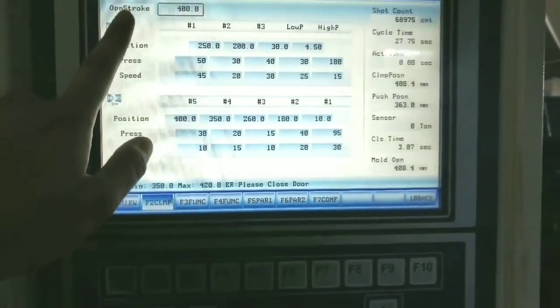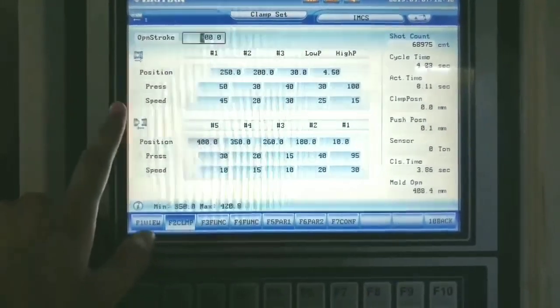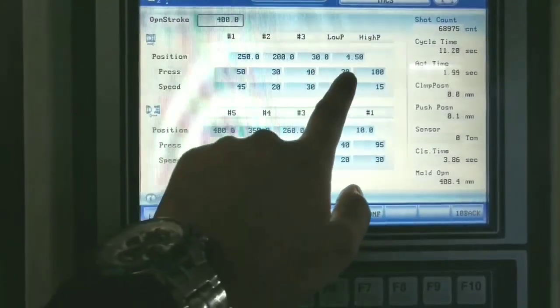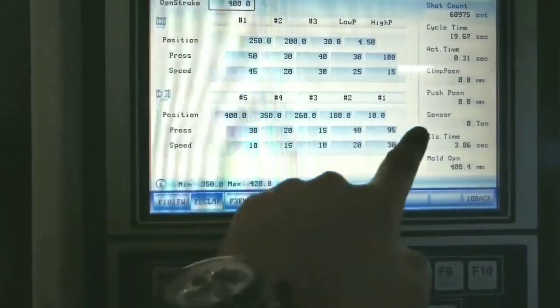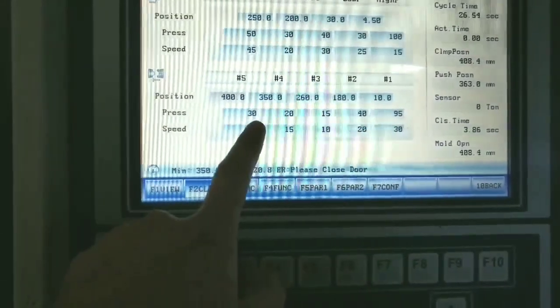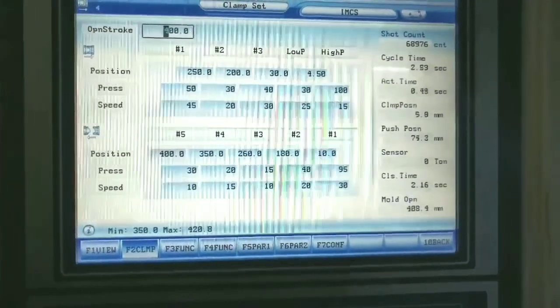I have pressed F2 and you can see the clamping page. It shows how much opening stroke has been set, along with position, pressure, and speed for each phase — first, second, third, low pressure, and high pressure. Mold open position, pressure, and speed — how the mold is opening on the first phase, second phase, and third phase, what the pressure and speed are — all these things you can see and change directly here according to the mold.